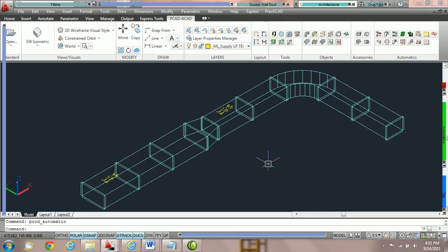The first change we're going to make is an elevation change. To change the elevation of a duct line, or to move it up a specific amount as a duct line as a whole, other than using the AutoCAD move commands, we can just simply click on the first fitting we'd like to change and then change the elevation of that fitting. If we move that fitting up 2 feet and all of the other ducts are attached, the entire system will move up 2 feet.